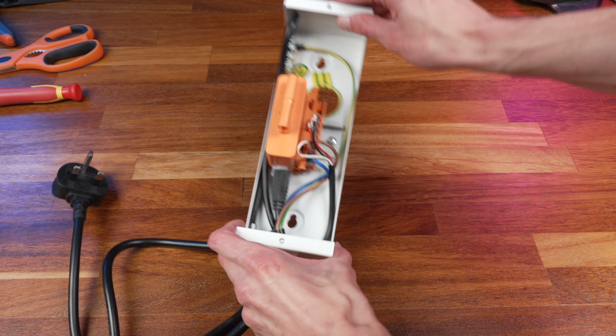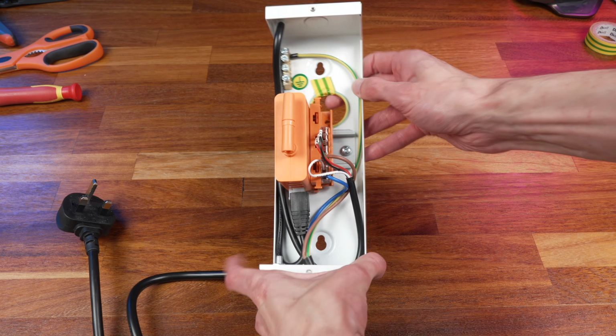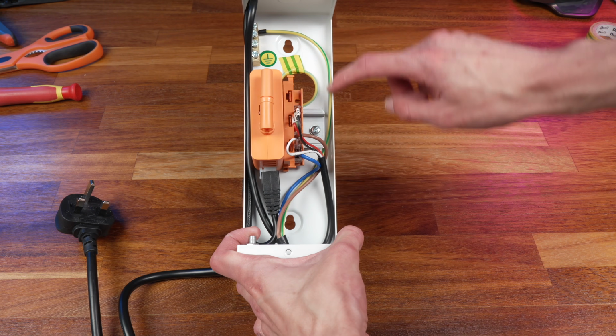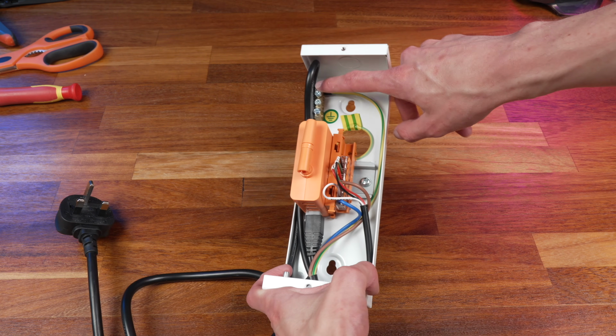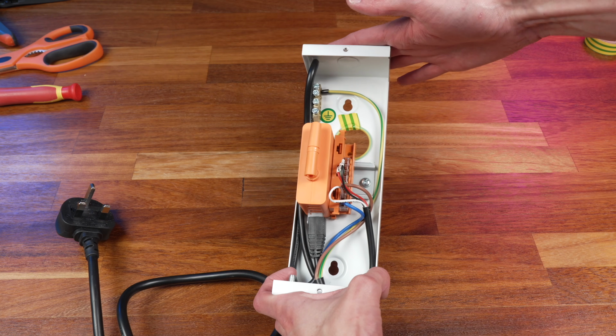And then the flex comes in the bottom. The CPC or earth then comes up the side here and connects into the earth terminal. So that just earths the whole case. The stuff inside doesn't need it. It just needs to earth the whole case.